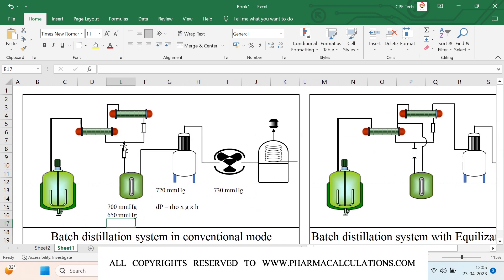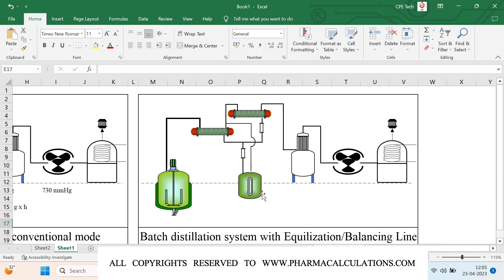In the conventional mode, whenever condensate flows from the condenser into the distillate collection receiver, a certain amount of pressure is generated due to the flow of distillate. At the same time, due to the flow of distillate collection, some uncondensed vapors enter the collection receiver and are sucked into the pre-condensing trap where they are collected. In the modified system with a balancing line, the vacuum is first generated in the secondary condenser, then in the primary condenser and receiver, and then in the reactor. The balancing line is added to maintain the same vacuum inside the receiver.